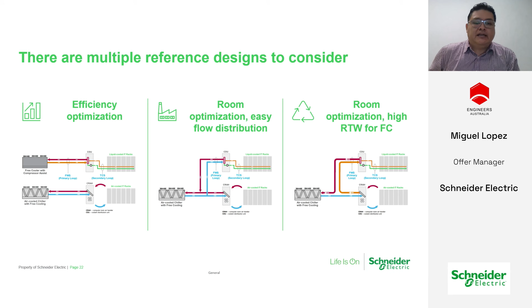And last but not least, the right-hand side image is showing where you could do a kind of in-series design of your water pipes, where the heat absorbed by your CRAH or your air conditioning unit is then delivered to your CDU. Once again, which reference design is best suited for your project or your customer's project will be governed by making sure we substitute correct water temperatures, all stemming from the water temperatures that the chip manufacturer is requiring. That will determine the need to backward engineer whether we deploy any one of these three reference designs.